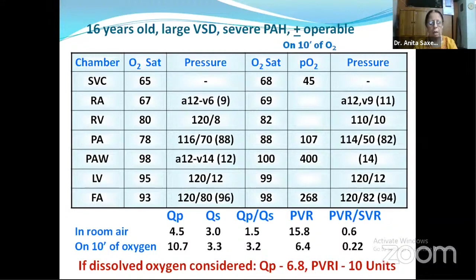So I'm going to just finish by giving you maybe 1 or 2 slides. One is, what are the sources of error in the cardiac cath lab? Something that you have to always keep at the back of your mind. I told you about the transducer level. I think you need to see how your pressures look, whether they are underdamped or overdamped. So you have to deal with it accordingly. Sometimes you're in a hypertrophic ventricle like an RV, you can wedge your catheter, especially the end-hole catheters, or even a multipurpose, where your pressures may become very high with a tall peaking. Use of a multi-hole catheter for withdrawal gradient should not be done, and therefore you should not try and interpret such pressure data, especially for gradients.